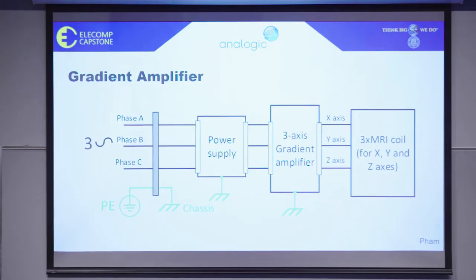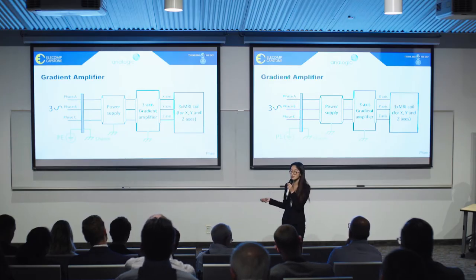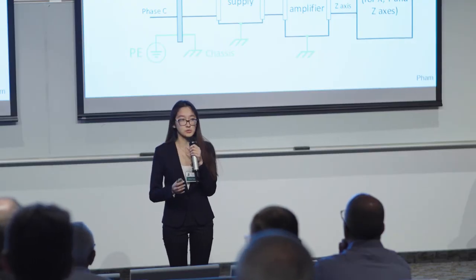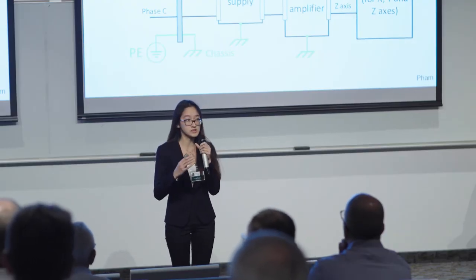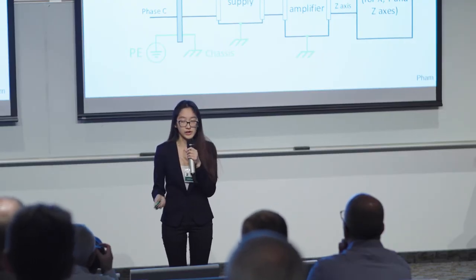In order to operate an MRI, users will specify a control waveform, and the gradient amplifier will work to provide both the power and signal amplification necessary to generate those magnetic fields. Now, under certain conditions, this input waveform can cause a gradient amplifier to exceed its operable levels, leading to system failure.